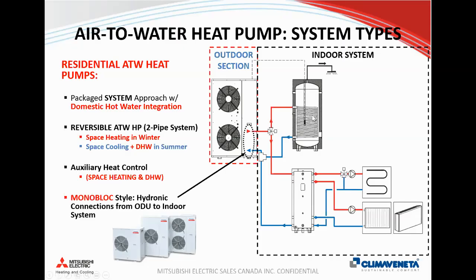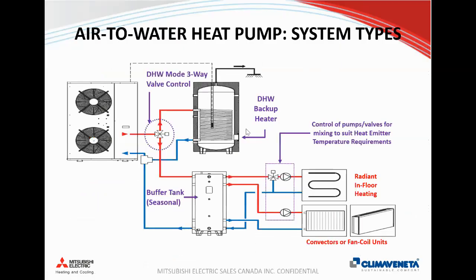Typically, these types of heat pumps will have internal control logic that will allow priority. So for example, in the morning, if 4 or 5 people get up and have a shower right in a row and you've depleted all the hot water in that tank, there's either schedule or priority that you can assign within the logic of the heat pumps to basically manage that. But point is, it's one system that we put into the house to do the job at all times, which is a little bit easier to do than on the commercial side. Basically with the heat pumps, it's also monoblock as well, so water connections between the outside and inside of the house. So again, this is just showing through a valve to control the domestic hot water production in the tank.